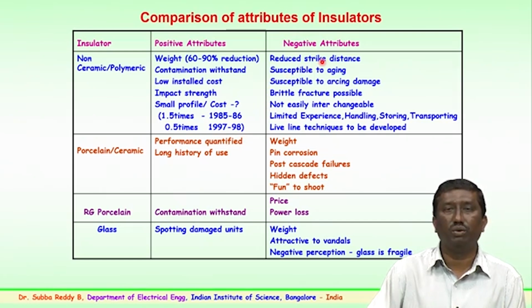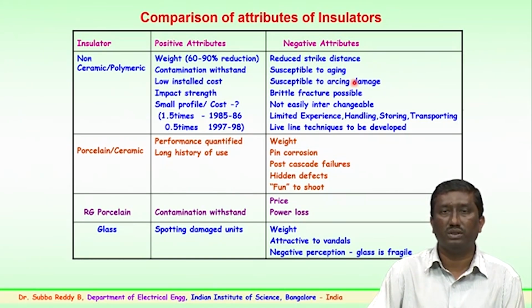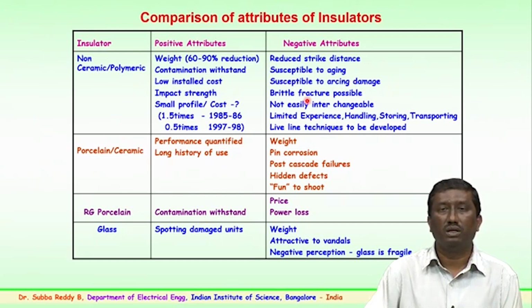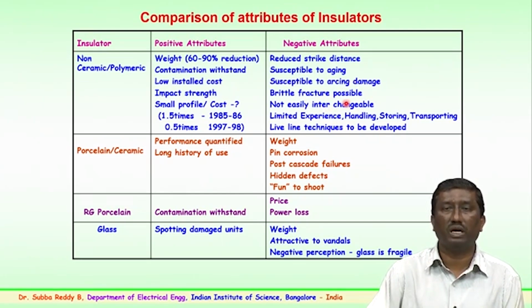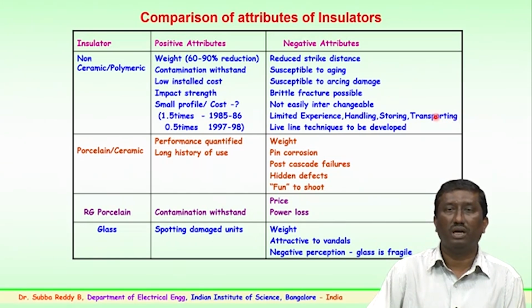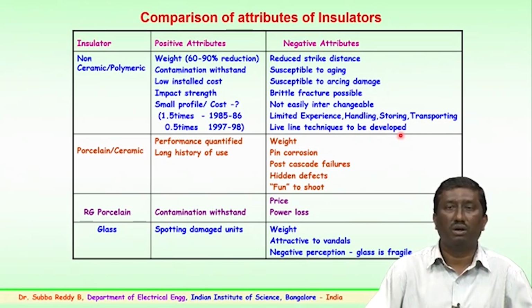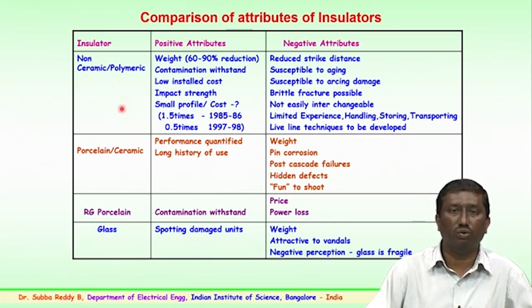Negative attributes, when you look into the non-ceramic or composite insulator: they have a reduced strike distance, and are susceptible to aging because the material is organic in nature. They are susceptible to arcing damage, brittle fracture has been noticed over a period of time, and it is sometimes difficult to interchange different types of insulators because of different designs. And as mentioned, they have limited experience. So handling, storing, transportation and live line techniques are still to be developed. These are very important because the technology is newer, so a lot of issues which are cropping up have to be addressed, whereas porcelain or ceramic performance has been quantified with a long history of use of more than 100 years.